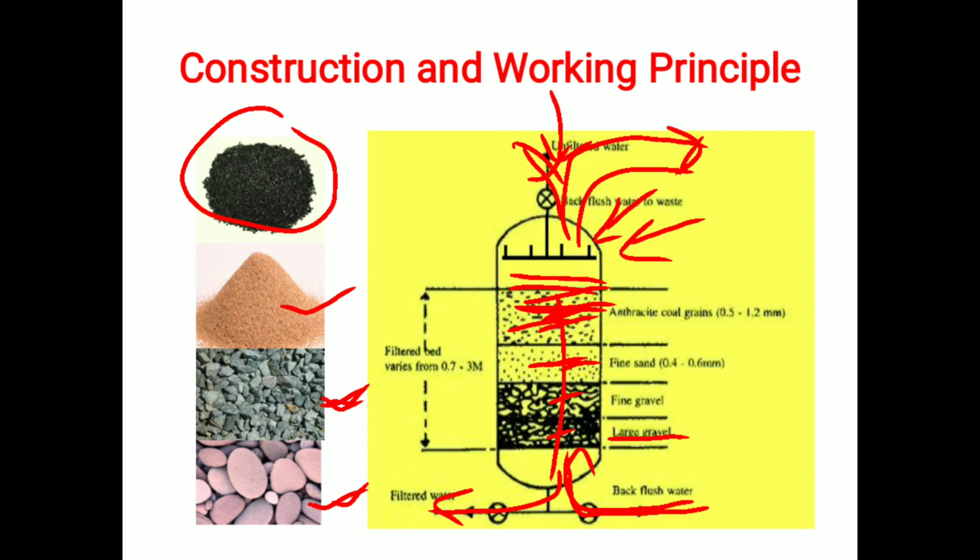Okay, the thickness of this media varies from 0.7 meter to 3 meter. It depends on the capacity of this filter. Okay, for large capacity the thickness of the filter media is very high, and for small capacity the thickness of the filter media is less. Okay, it depends on the capacity.